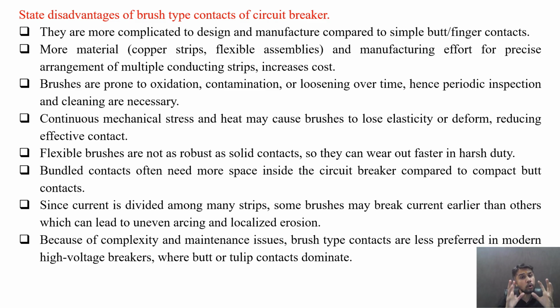Brushes are prone to oxidation, contamination, or loosening over time. Hence, periodic inspection and cleaning are necessary. Continuous mechanical stress and heat may cause brushes to lose elasticity or deformation, reducing effective contact. Flexible brushes are not as robust as solid contacts, so they can wear out faster in harsh duty.